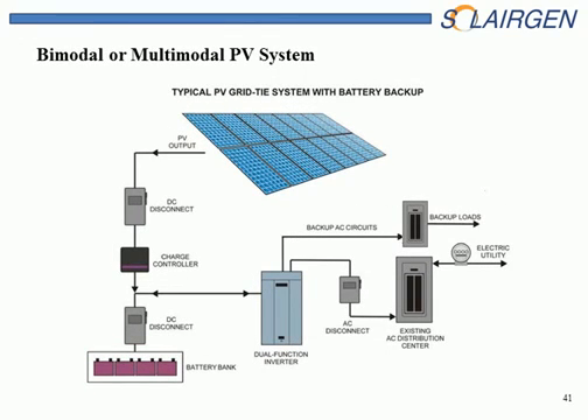With a bimodal system, you may have an interactive bimodal system where this inverter, same as the standalone inverter, would operate to sell excess power back to the utility. Then again, it may be a non-sell type of multimodal inverter, where it can operate off-grid in a lot of different modes. In that case, it becomes a standalone system, and you wouldn't see the AC disconnect. It's supposed to be outside, but like I said, there's no utility to force that unless they're selling power back to the utility. So in either situation, what you have is the possibility of a PV system feeding into a battery, into an AC panel with no exterior access. It's required to be there, but if the enforcement's not in place, then it could be that the AC disconnect is interior.